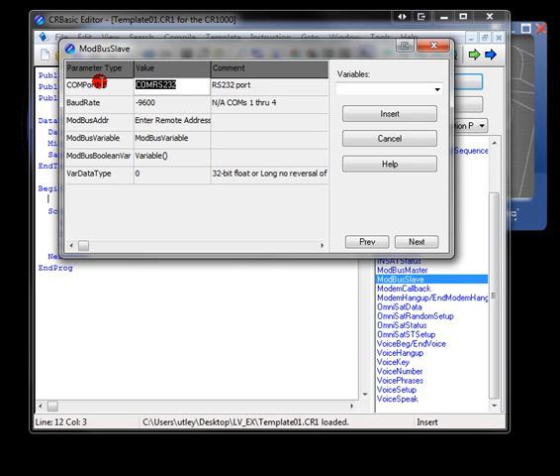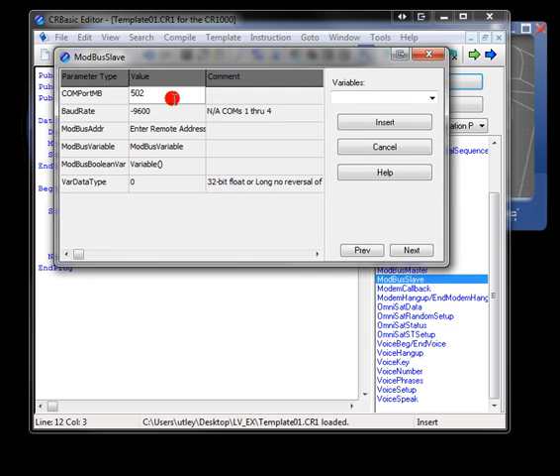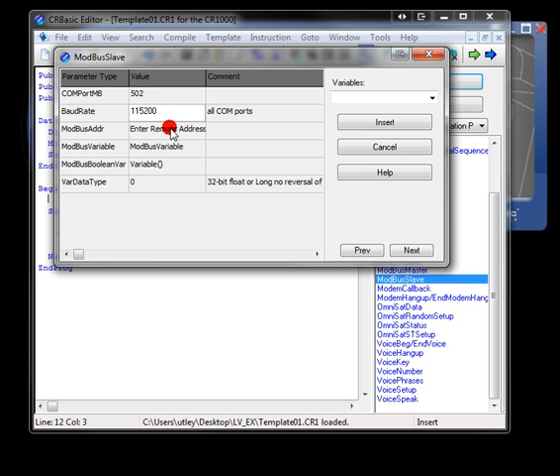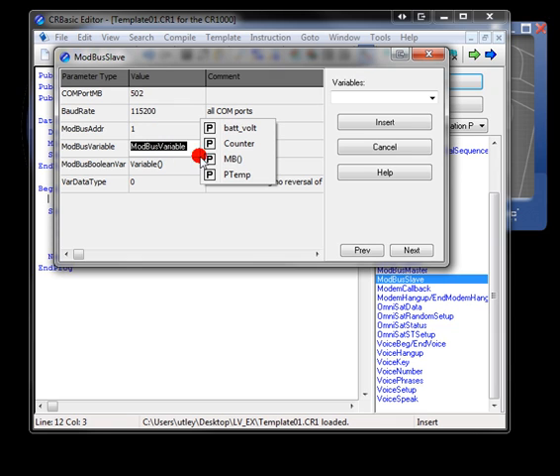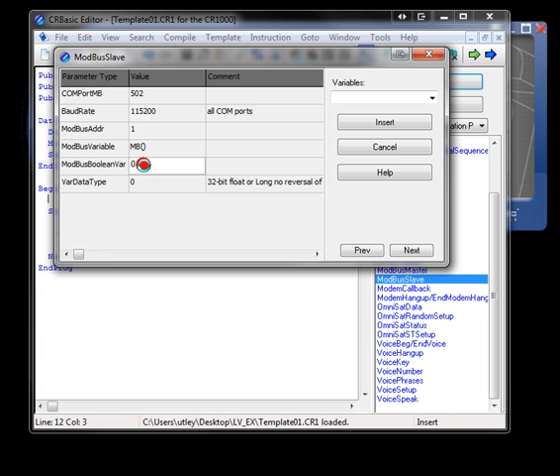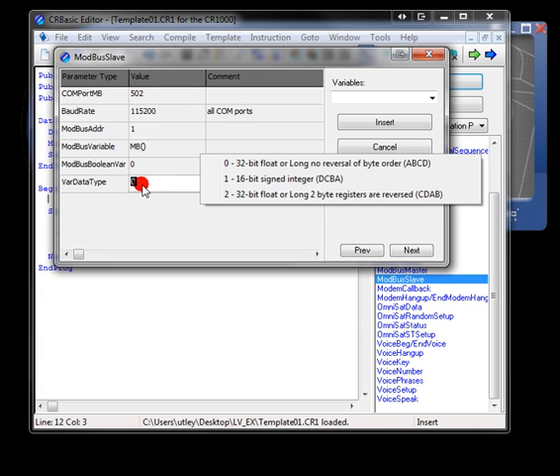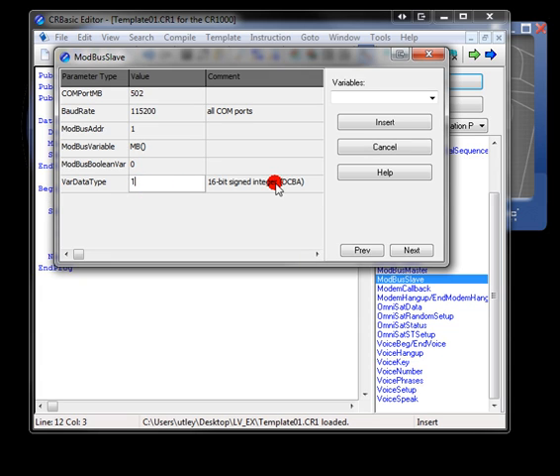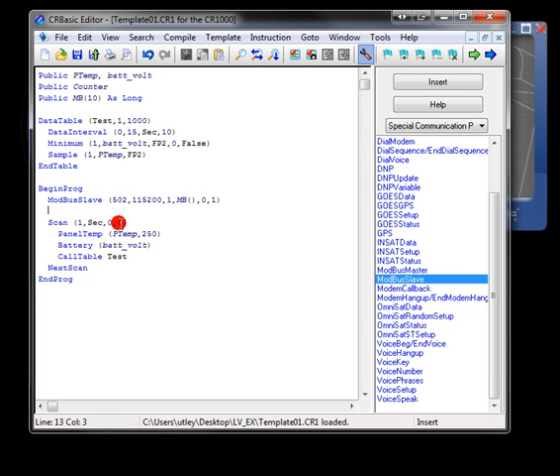Having done this a couple times, first thing we're going to do is set the data logger up to communicate on IP port 502. Then we're also going to select some baud rate. It doesn't really matter here - we are performing communications over TCP IP, not over a serial port in this case, though that is possible. We'll also give the data logger a Modbus address. We'll tell it that its registers should be mapped to the array that we set up earlier called MB. Then we're going to set the Modbus Boolean var parameter to 0, instructing the data logger to map its input coils or coils to control ports 1 through 8. Then we're going to select the data type of 16-bit signed integer and insert the instruction.